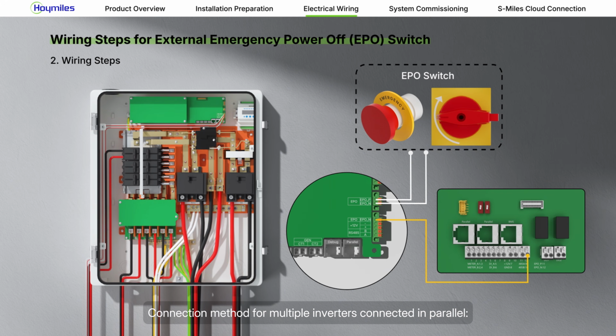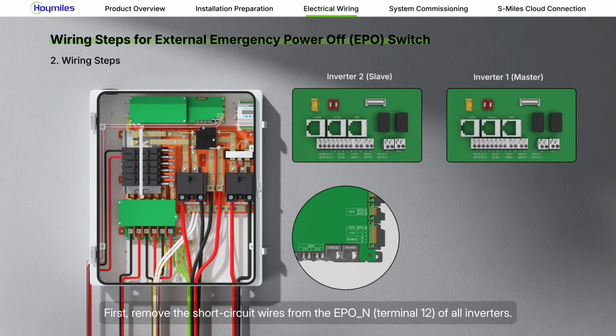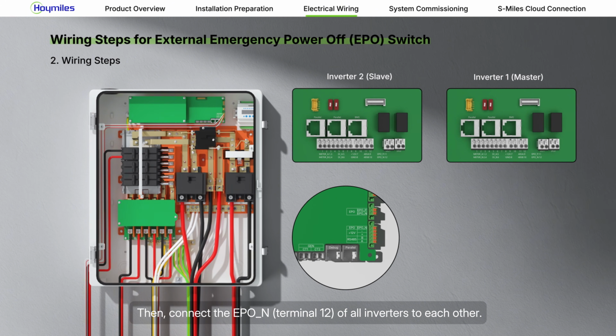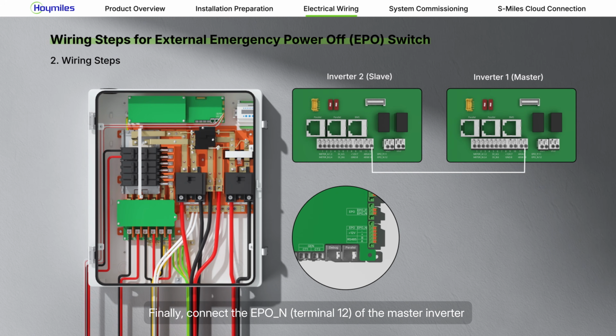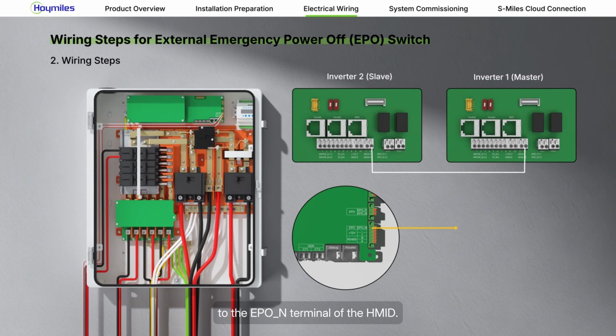Connection method for multiple inverters connected in parallel. First, remove the short circuit wires from the EPO-N of all inverters. Then, connect the EPO-N of all inverters to each other. Finally, connect the EPO-N of the master inverter to the EPO-N terminal of the HMID.